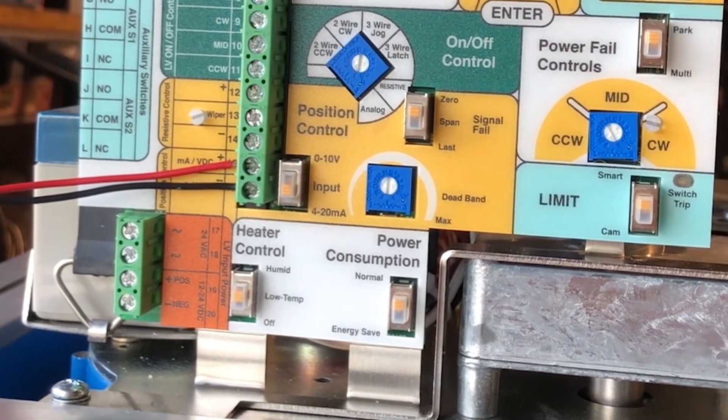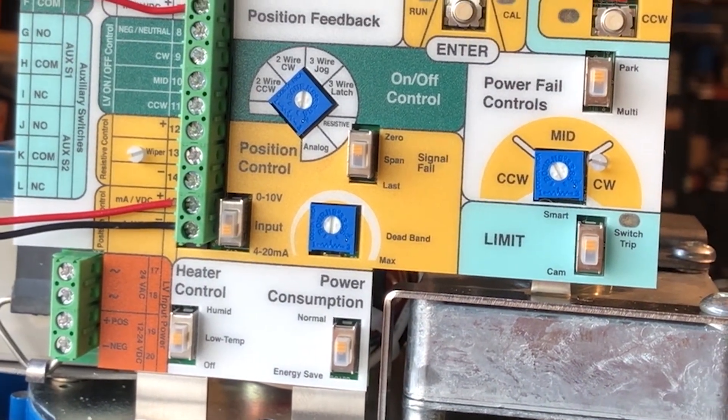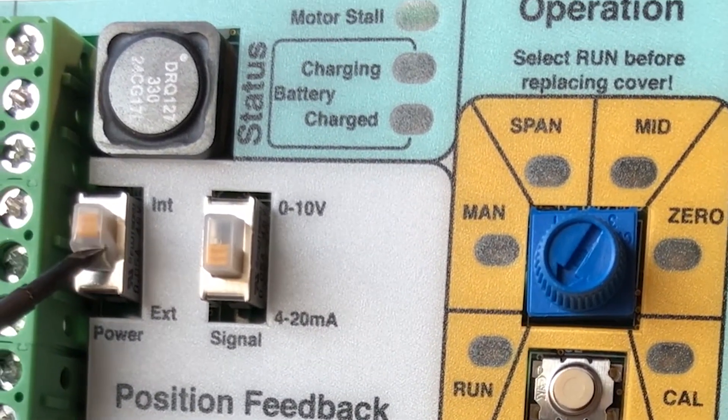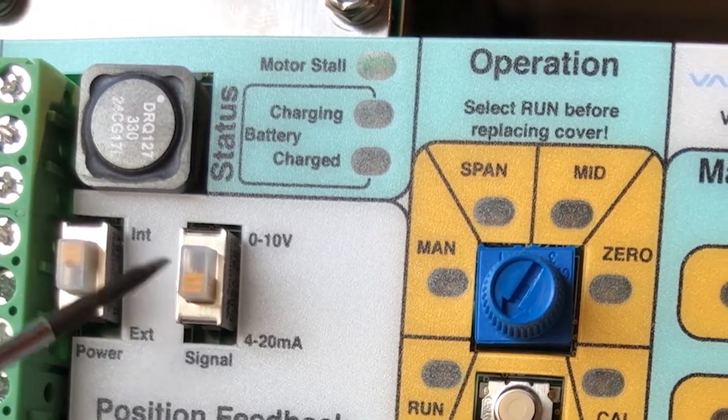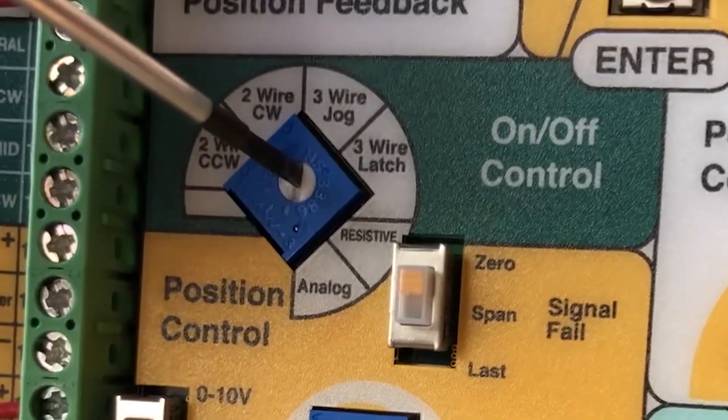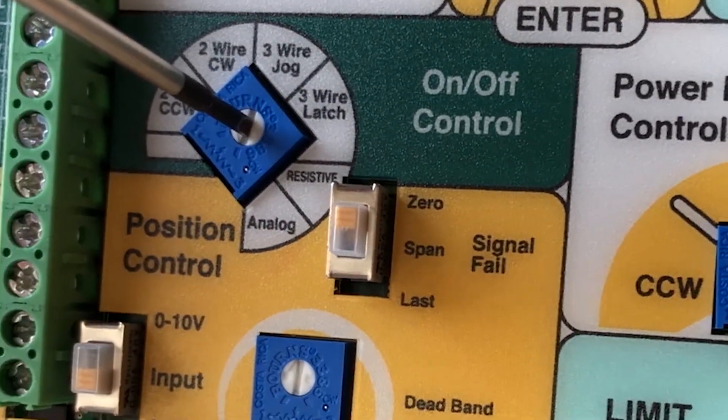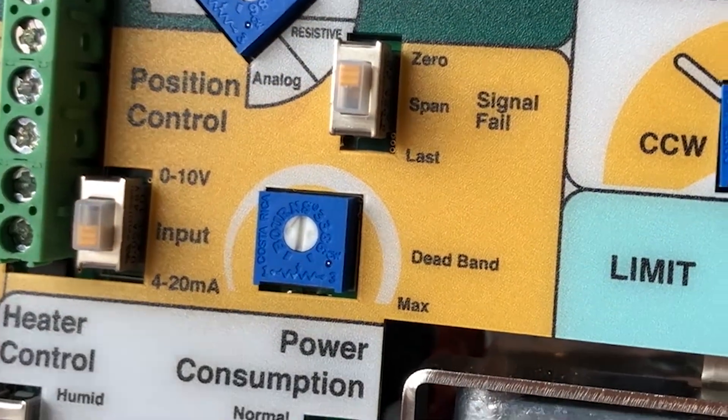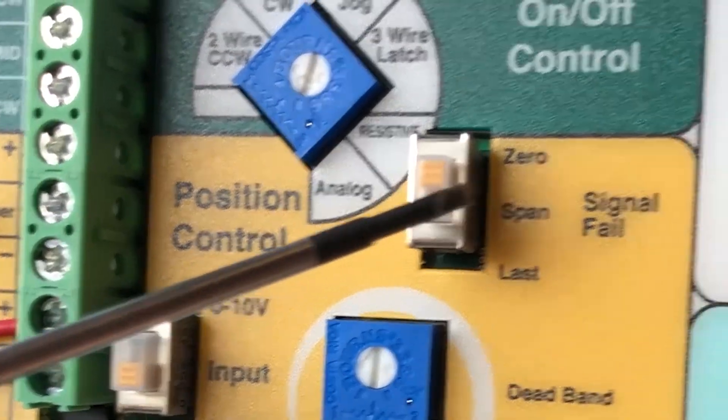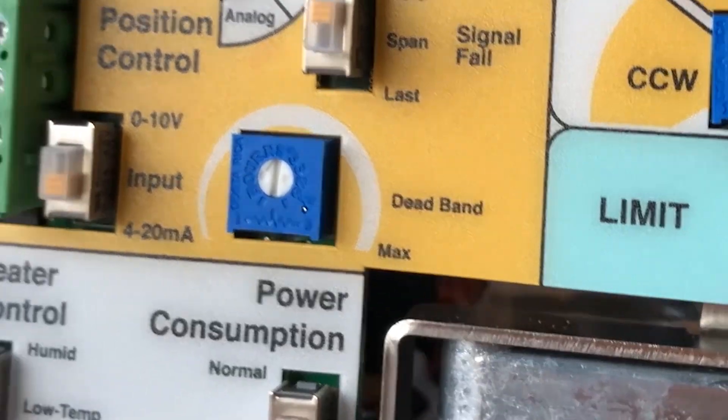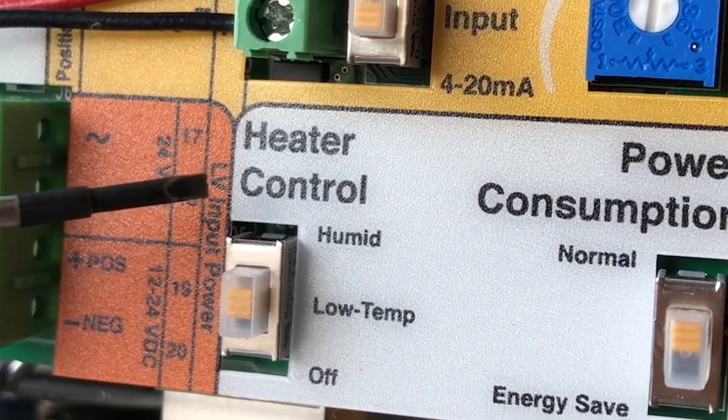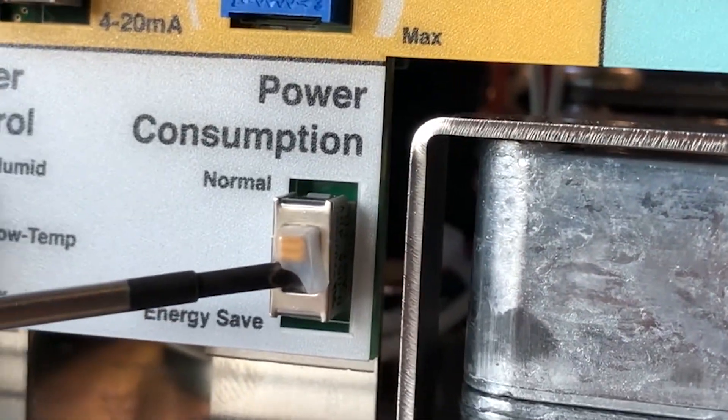Before we power on our actuator we're going to check the dip switches on our board. So first we're going to start up here in the position feedback. I want to verify power dip switches in the internal position. Our signal is in the 4 to 20 milliamps. Our on and off control dial is verified that the arrow is pointing down to the analog. Our position control is 4 to 20 milliamps. Signal fail is zero. Heater control for your location is going to be in the low temperature position. Power consumption is in the normal position.